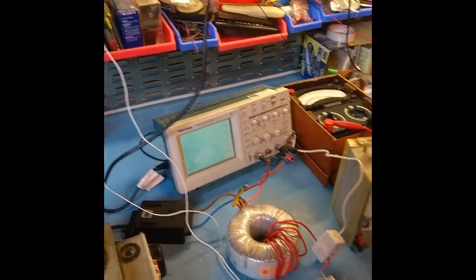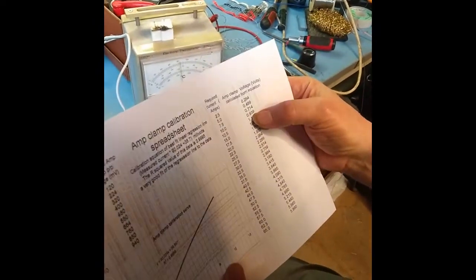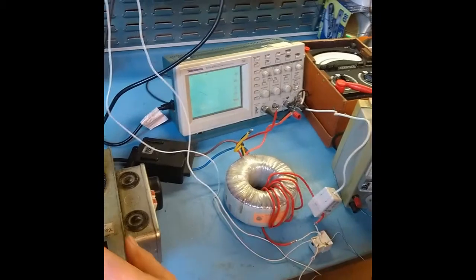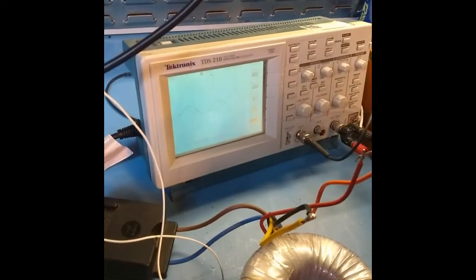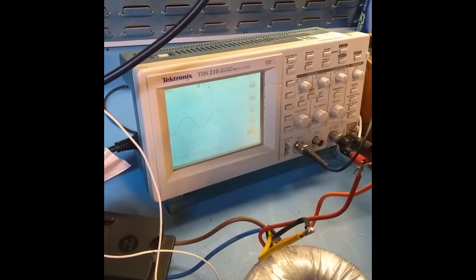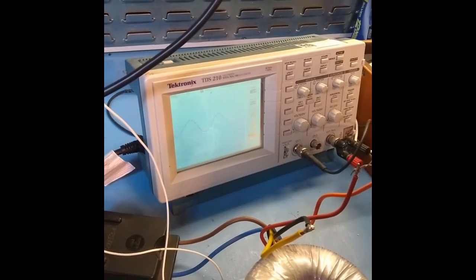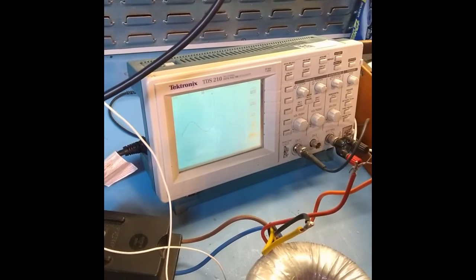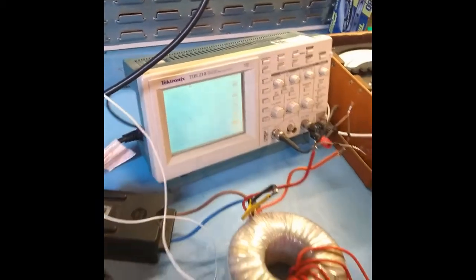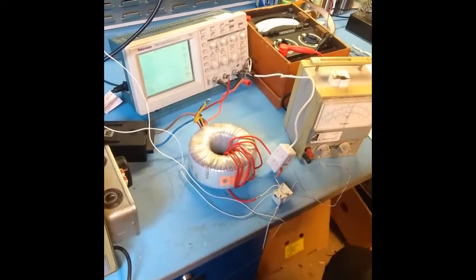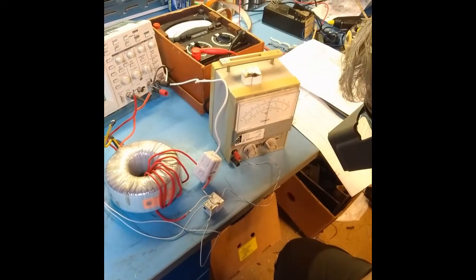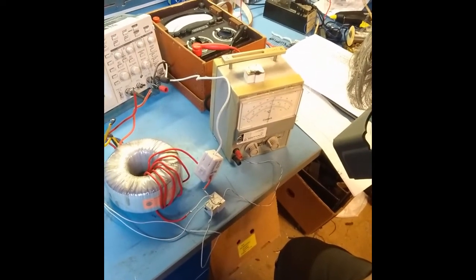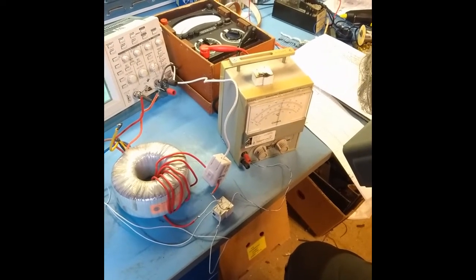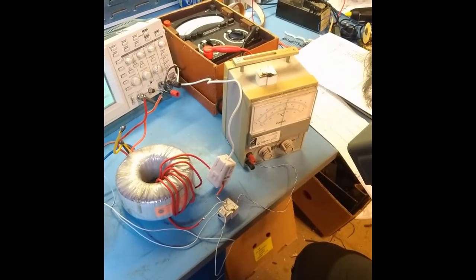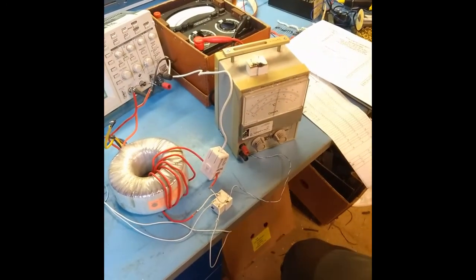And going to the calibration curve, we're going to start at 10 amps, which is 0.939 volts. Control from the variac isn't particularly precise. And the temperature is going up. We're going to take a break here while it stabilizes.